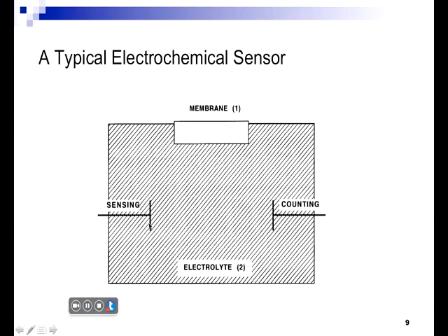And the positive charges will go on one side, the negative charges will go on the other side. You'll set up a gradient, and once you do that, you can measure it. It's like measuring the current that can go through this based upon the concentration gradient. So it's a real simple system, but it's very effective for a lot of gases and vapors that you can create ions with. And again, the problem with leakage is that this can break. It's in a sealed system, but it can break out, and if it does that, then it can leak and cause a problem.